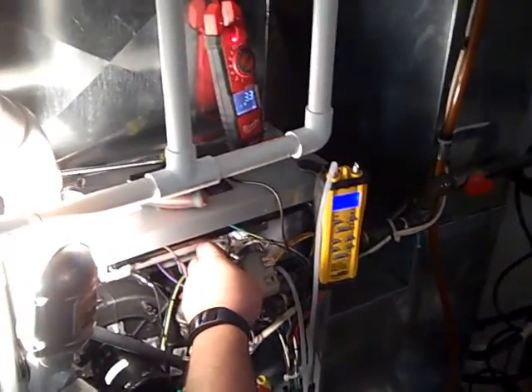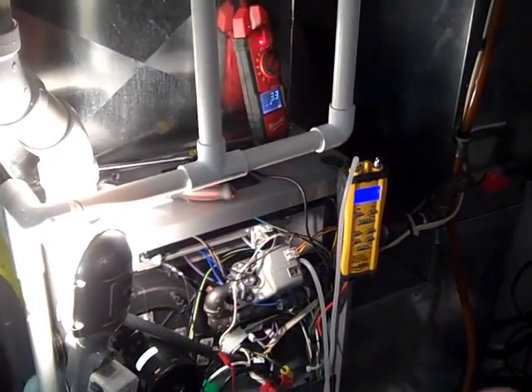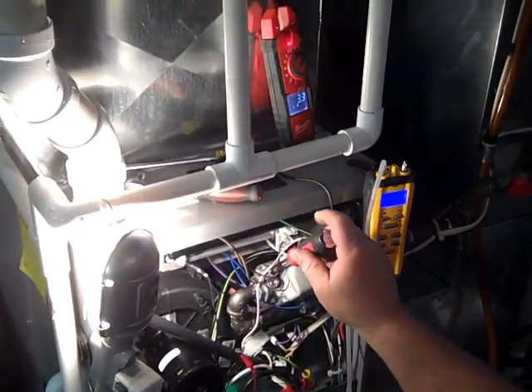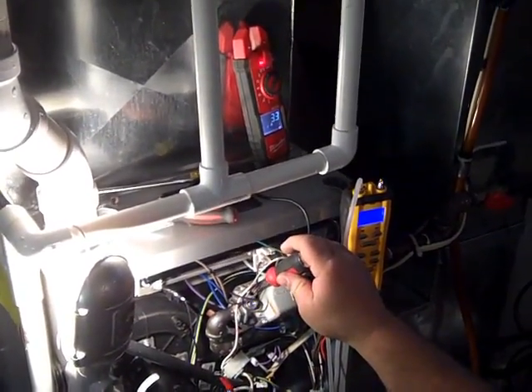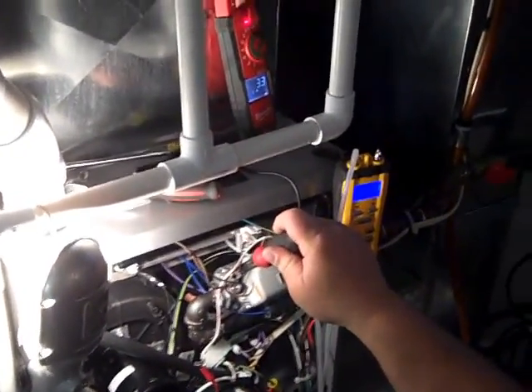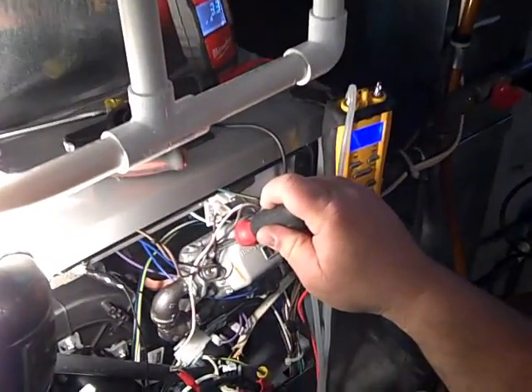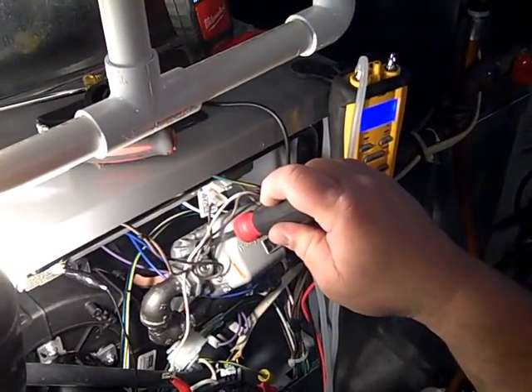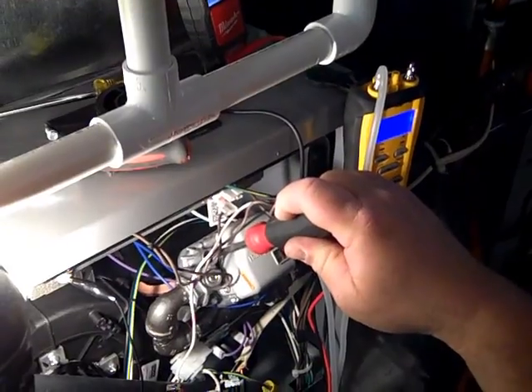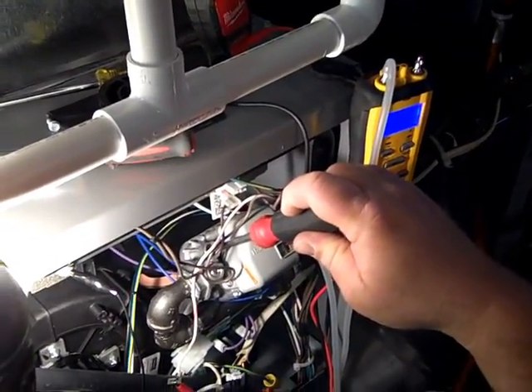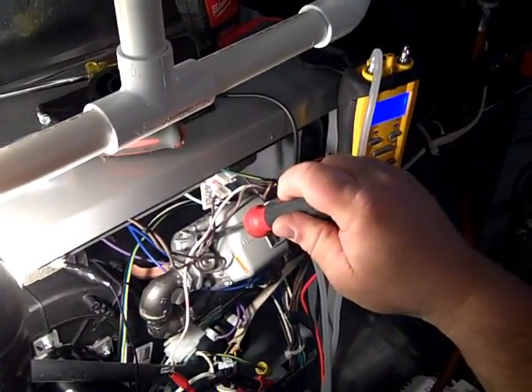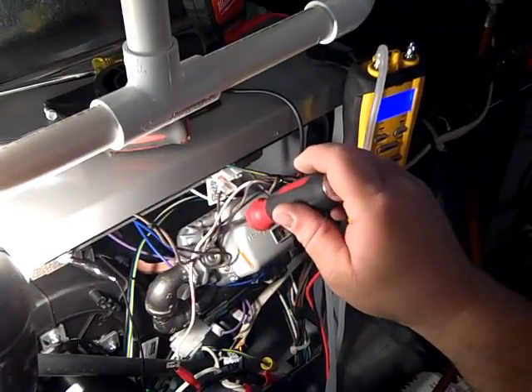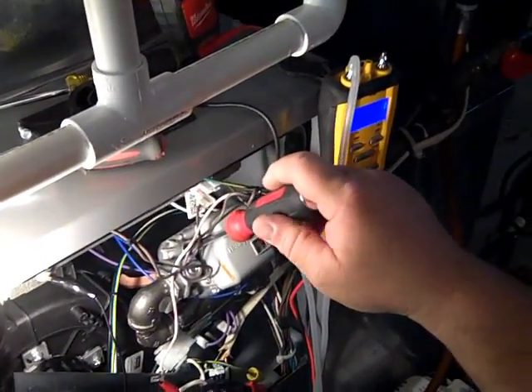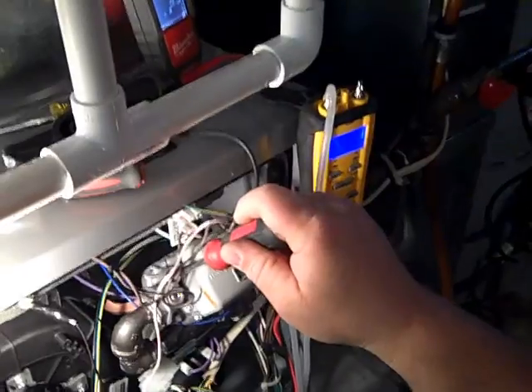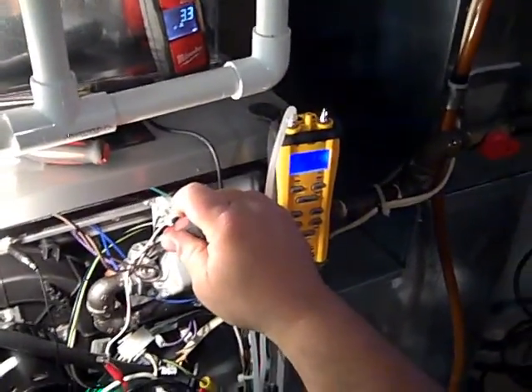We've talked about it in class. We have to know that information. You have to get the temperature rise. And he gets the opportunity to adjust the gas valve if the gas pressure is a little too high or a little too low. Remember what we talked about, especially if it's too high, you'll end up tripping out flame rollouts and thermal limits and some of those other things. So you want to make sure the gas pressure is right where it needs to be.